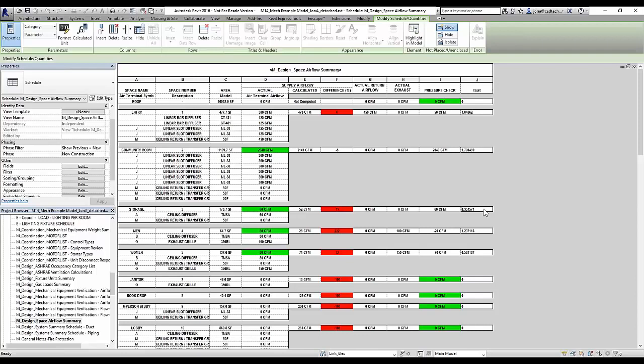So we can use these as a quick indication of where we might need to look. Green was probably a poor choice, but we can utilize this to say, okay, I realize that I'm probably not at the right CFM. And maybe I need to bump this storage space up if I'm looking for 1 CFM per square foot.